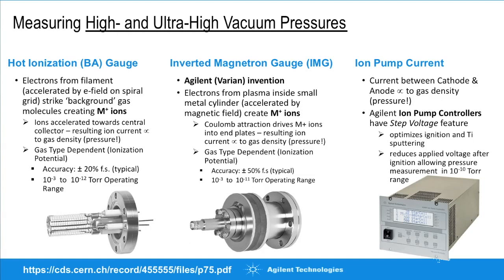If using a sputter ion pump, the current between the anode and cathode is directly proportional to gas density or pressure inside the pump. Agilent controllers use a step voltage feature — a very high potential creates the plasma discharge, then once stable, voltage is reduced to the minimum level possible. This reduces leakage current, improves measurement accuracy, and allows the ion pump controller itself to measure pressures down to the 10⁻¹⁰ torr range.